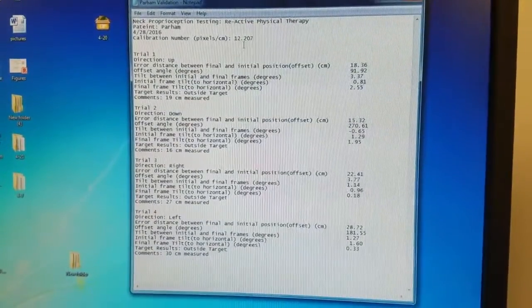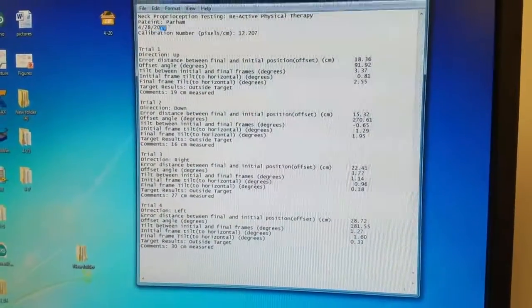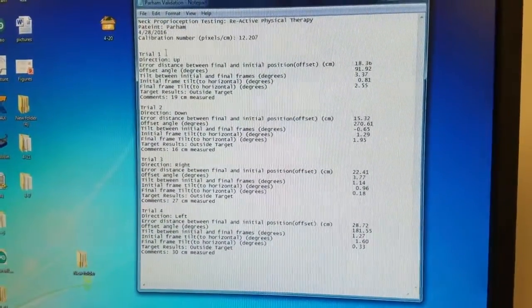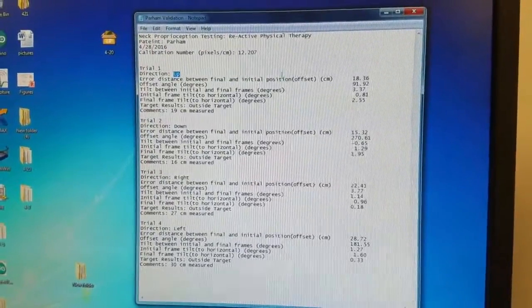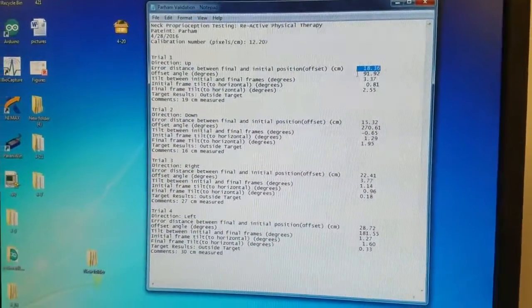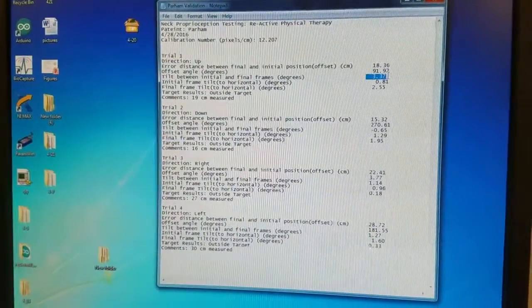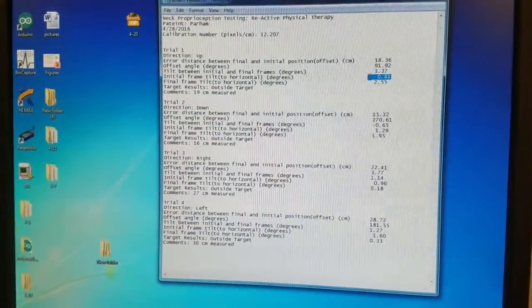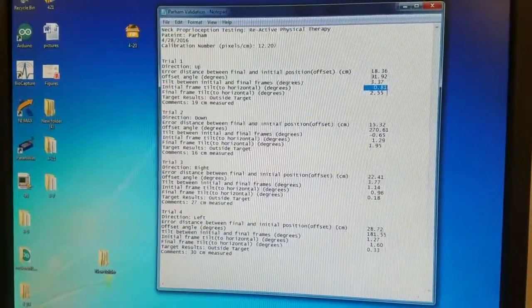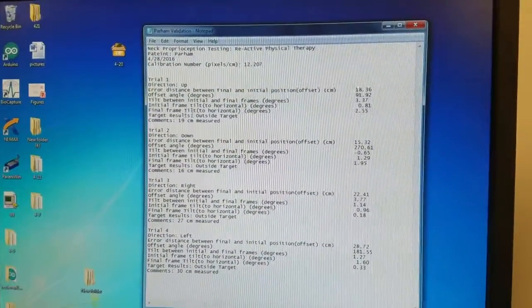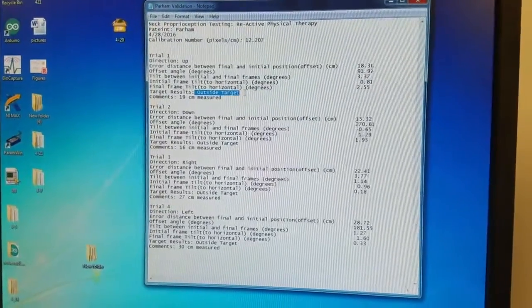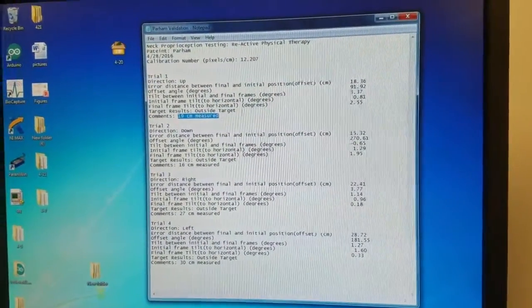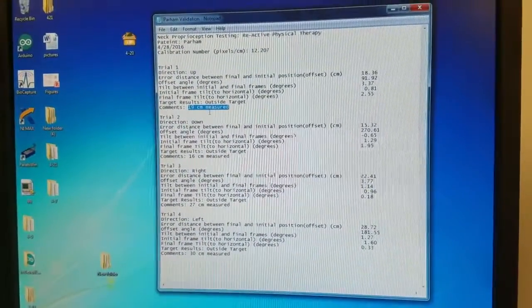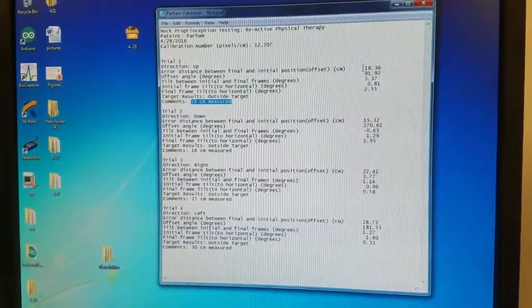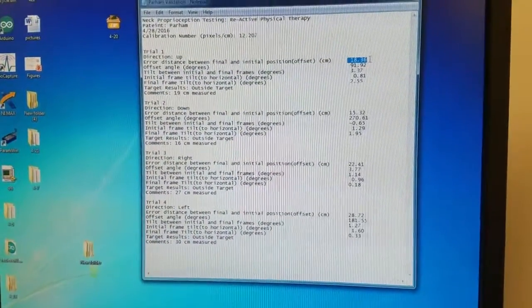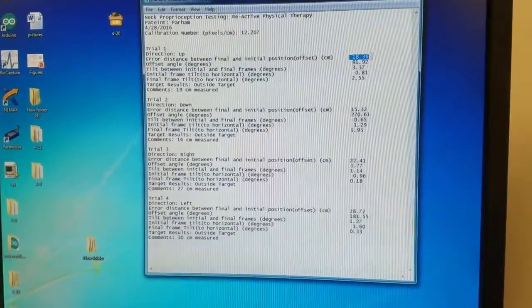Tests had a calibration number of 12.2, as we can see here. The date is automatically recorded along with the patient name that you entered. The first trial will tell you the direction that you chose along with the offset distance, the offset angle, and the tilt difference between your initial and final frame. And this is the tilt of your final frame, and this is the tilt of your initial frame. This results showed that the final dot was outside the target. This was a validation result, so we measured 19 centimeters with the physical ruler, and our distance calculated was 18.3, which shows that our validation is correct and the distance that we measure is correct.